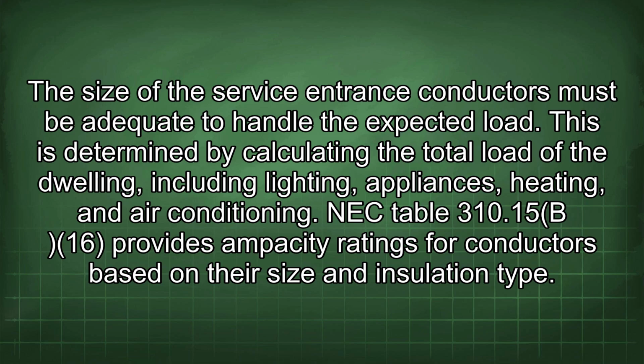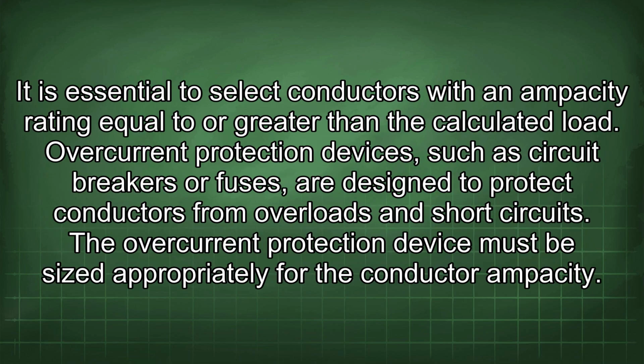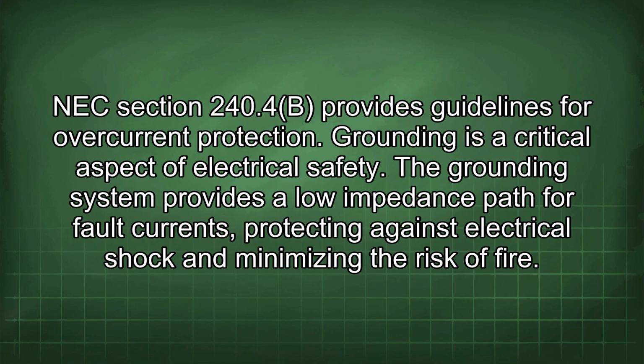NEC Table 310.15(B)(16) provides ampacity ratings for conductors based on their size and insulation type. It is essential to select conductors with an ampacity rating equal to or greater than the calculated load. Overcurrent protection devices, such as circuit breakers or fuses, are designed to protect conductors from overloads and short circuits. The overcurrent protection device must be sized appropriately for the conductor ampacity. NEC Section 240.4(B) provides guidelines for overcurrent protection.